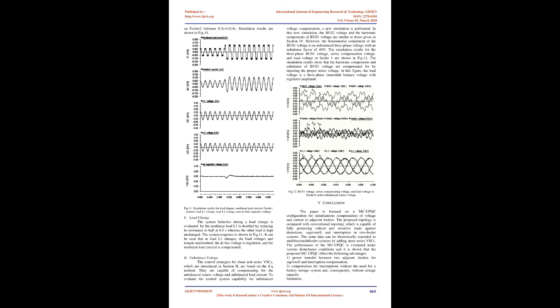In the proposed configuration, the sensitive/critical load on feeder 2 is fully protected against distortion, sag/swell, and interruption. Furthermore, the regulated voltage across the sensitive load on feeder 1 can supply several customers who are also protected against distortion, sag/swell, and momentary interruption. Therefore, the cost of the MC-UPQC must be balanced against the cost of interruption, based on reliability indices, such as the Customer Average Interruption Duration Index, CAIDI, and Customer Average Interruption Frequency Index, CAIFI.